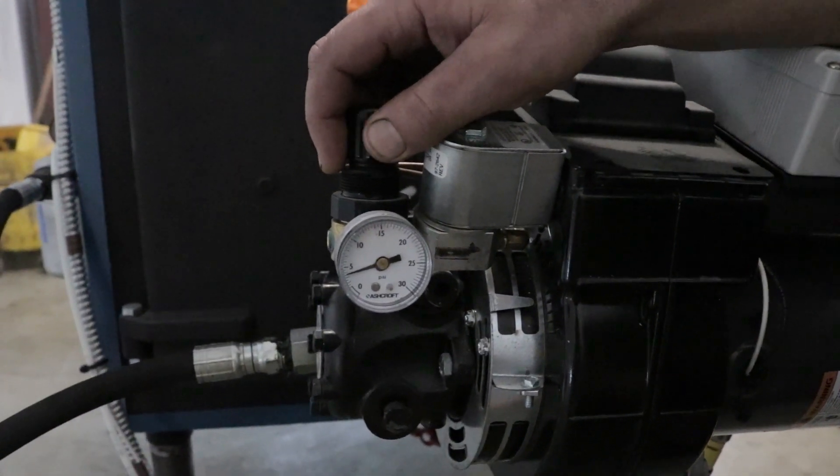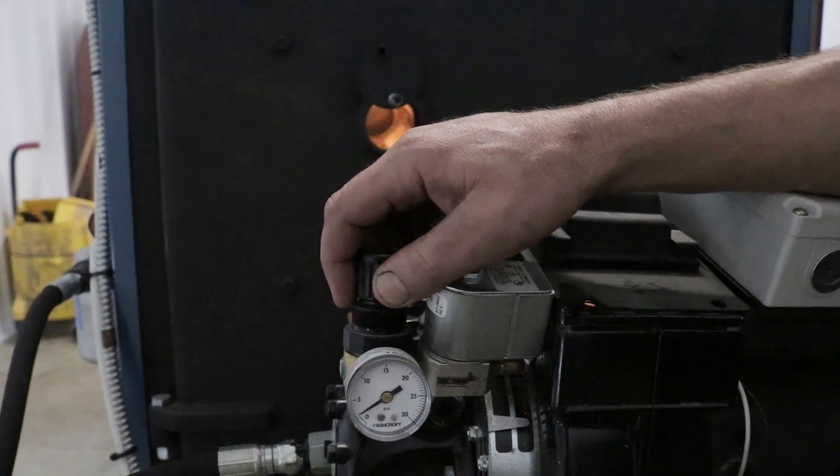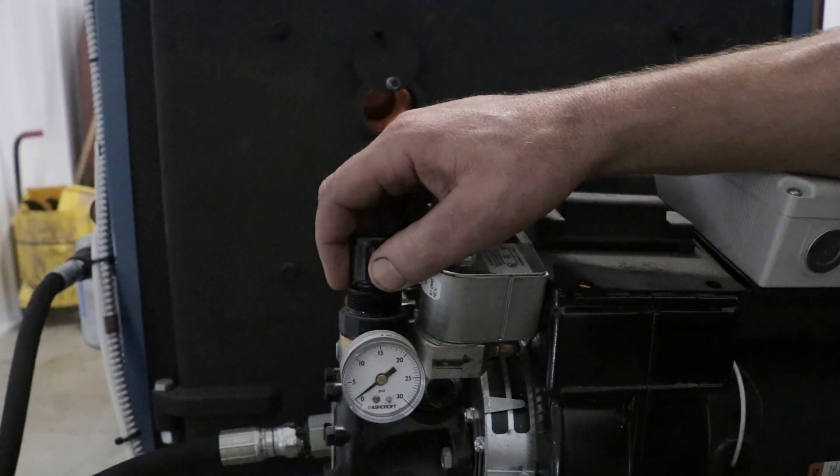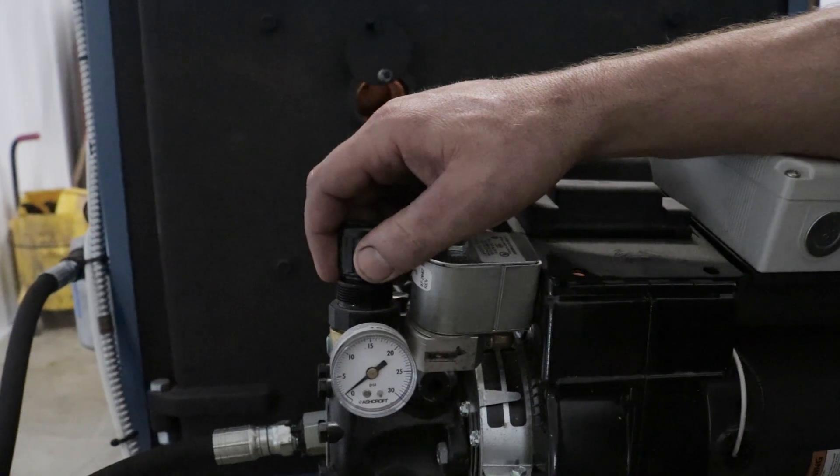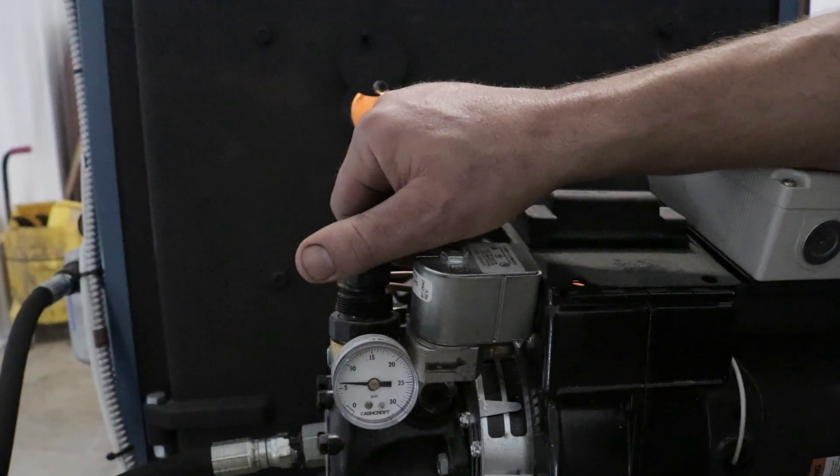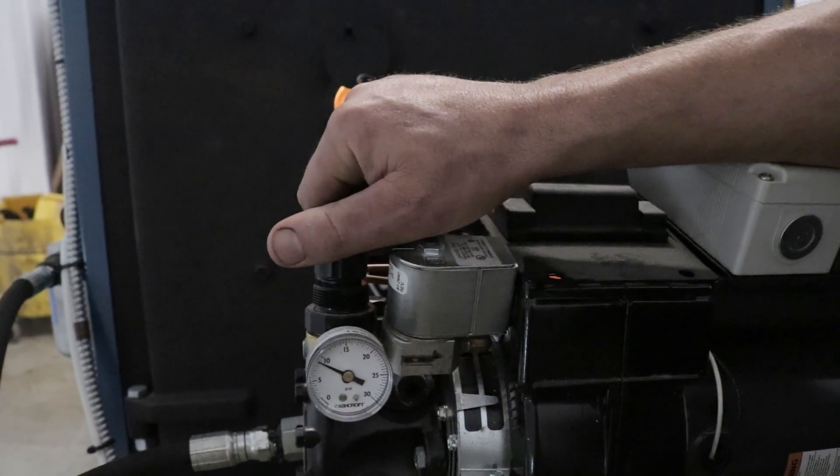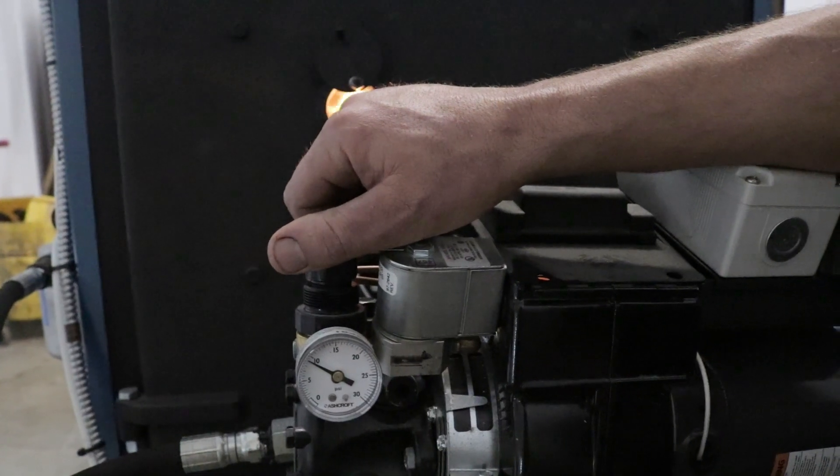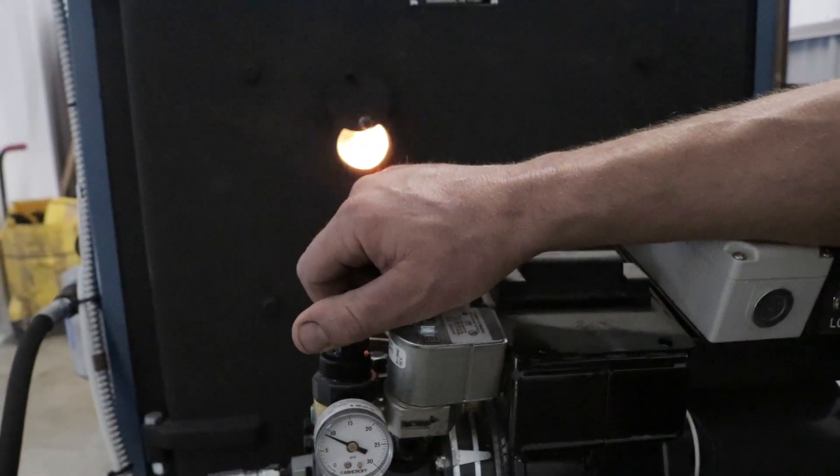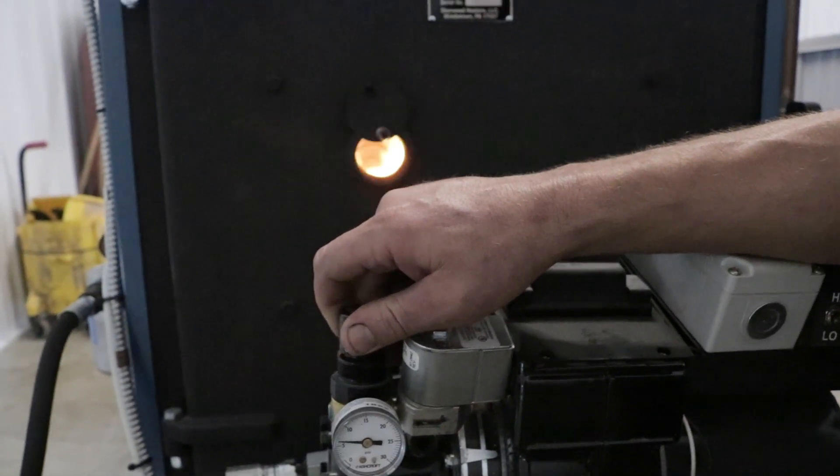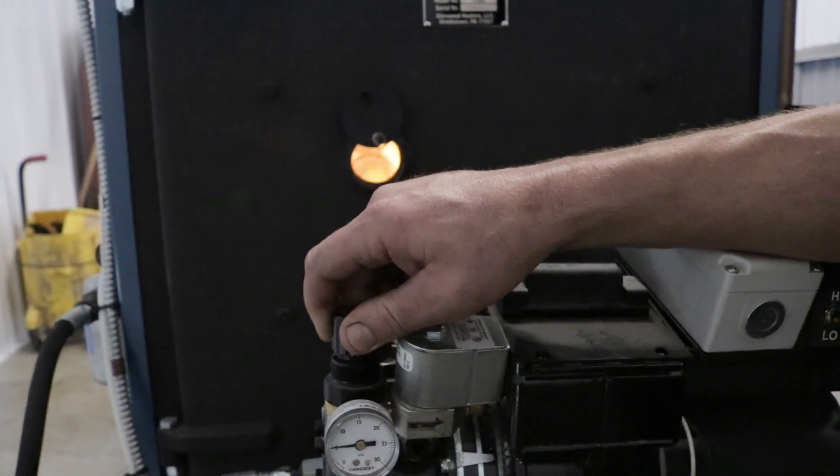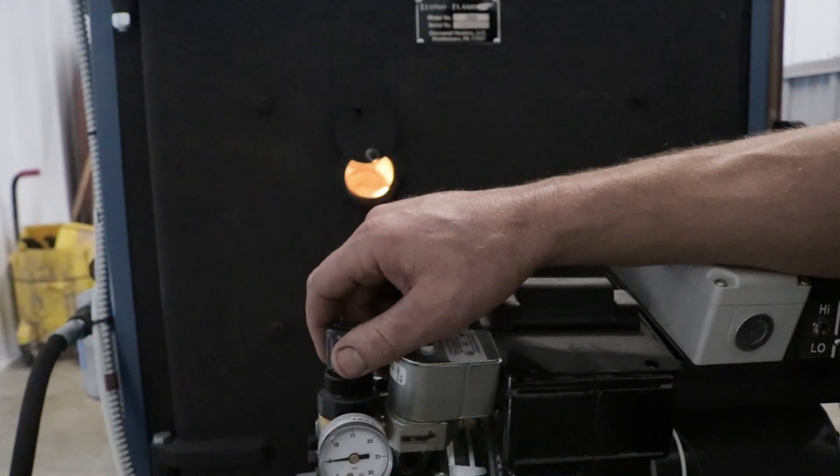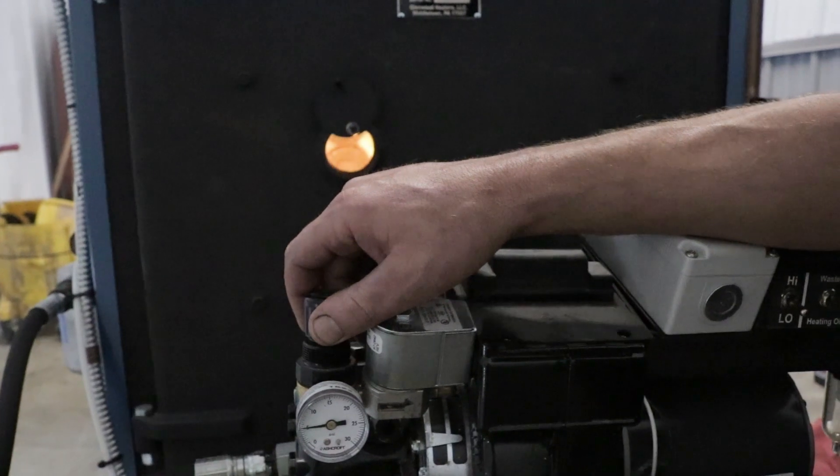If the oil flow is too lean, the flame gets short and it gets sparky. If it's too rich, the flame gets smoky. It starts rolling around in there and starts doing secondary combustion. The proper setting gives you a nice white, puffy flame without sparks and without smoke.